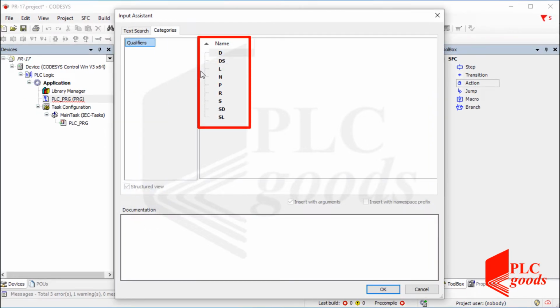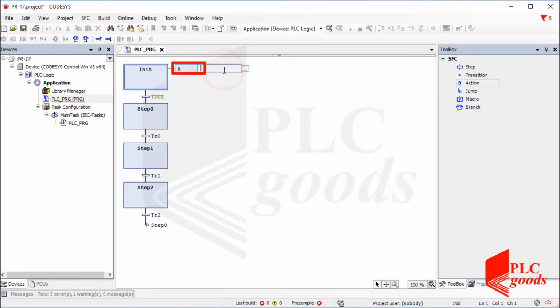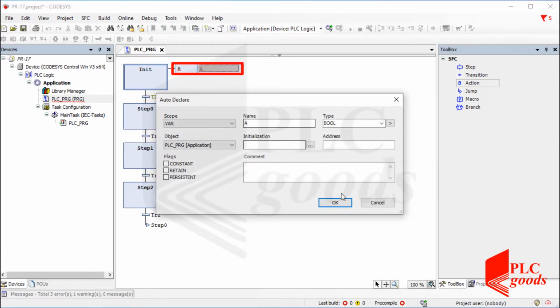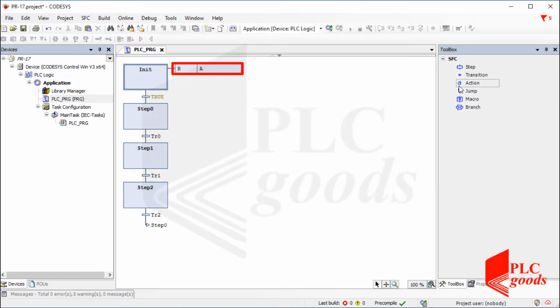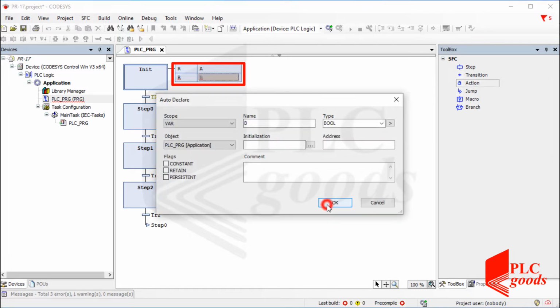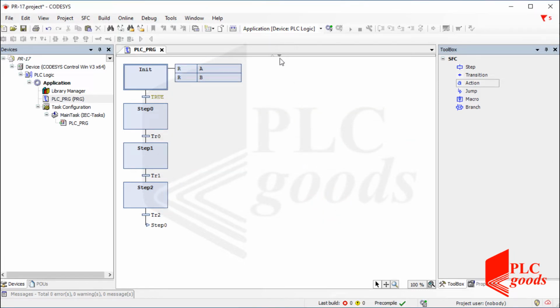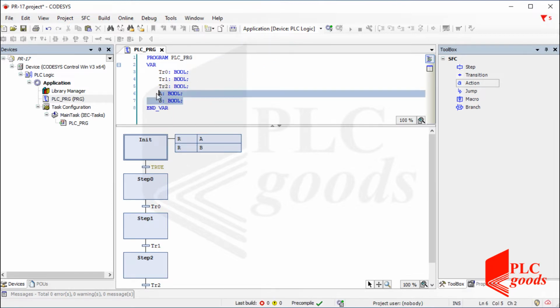Here you can see all of them. These three qualifiers, whose names are non-stored, reset, and set, are more common than others. This one can be used to reset a Boolean variable or digital output to 0. Note that, several IEC actions can be defined. They will be executed from top to bottom. Well, let's define two more variables, and reset them at the initial step.